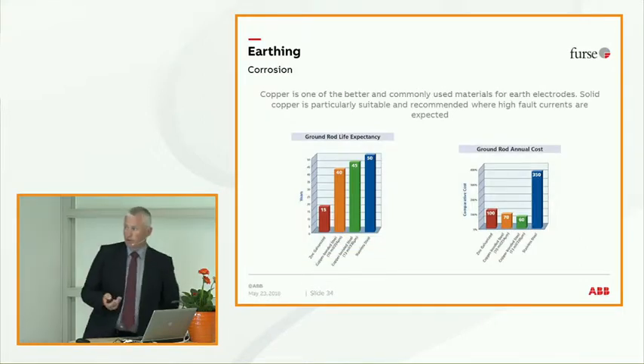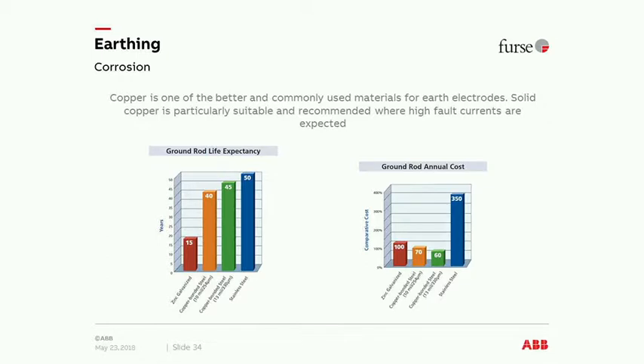Here's a graph we make reference to. If we're looking at the life expectancy, galvanized rod is 15 to 20 years. I know those examples are a lot less. And then it shows you the copper bond, different copper thicknesses, and the stainless steel by far outweigh the lifespan. So when we're doing a comparative cost, you can see that the zinc galvanized isn't effectively cheaper, isn't commercially beneficial, because you've got a cheaper option with a copper bond.